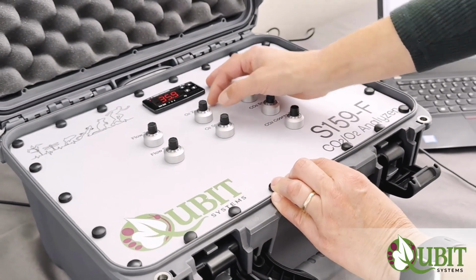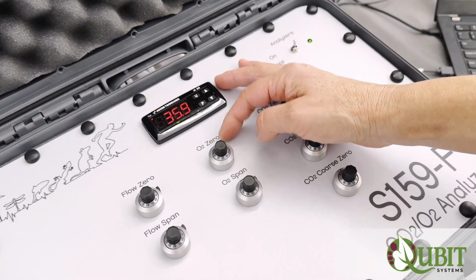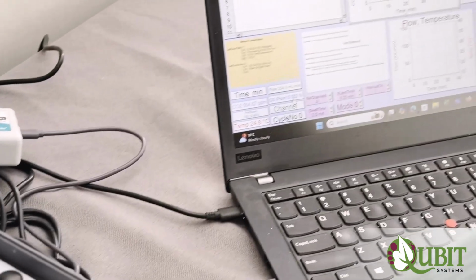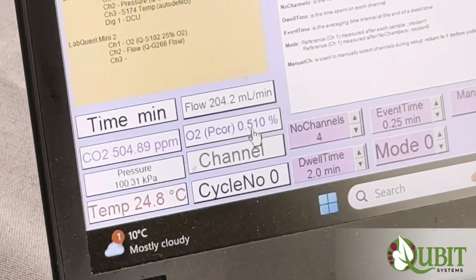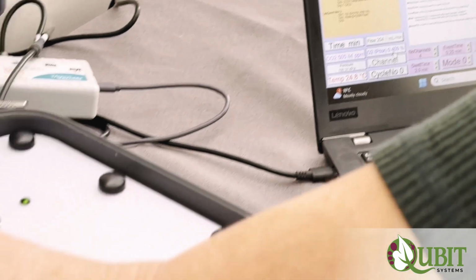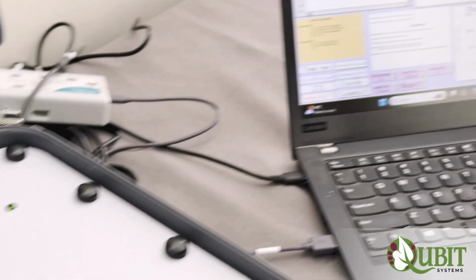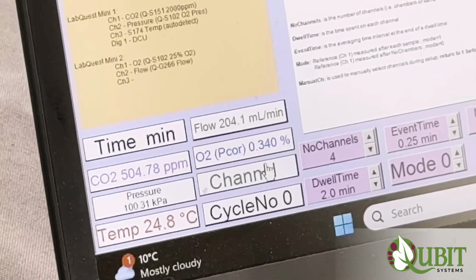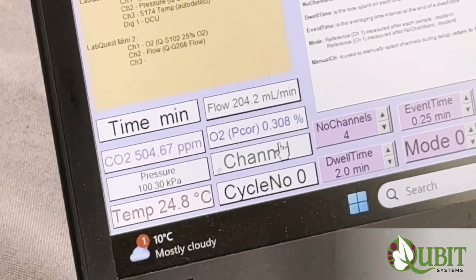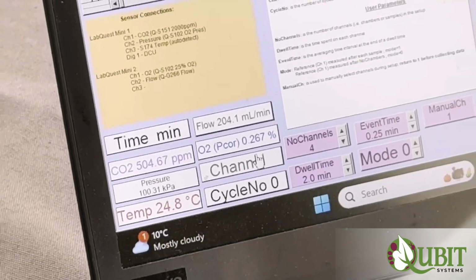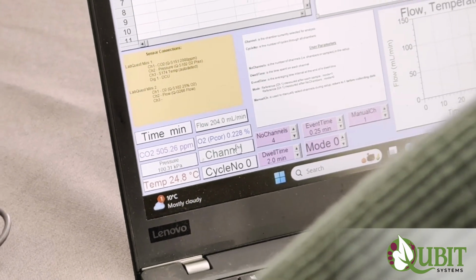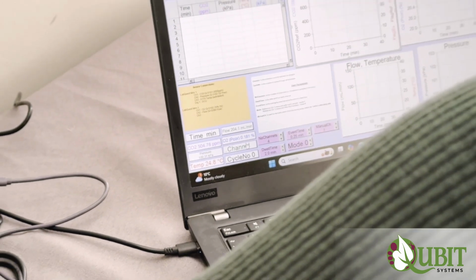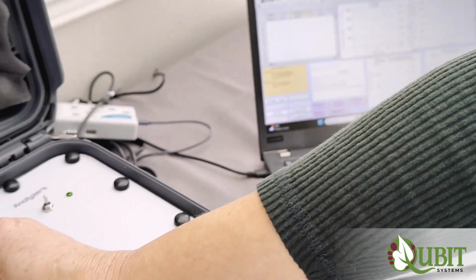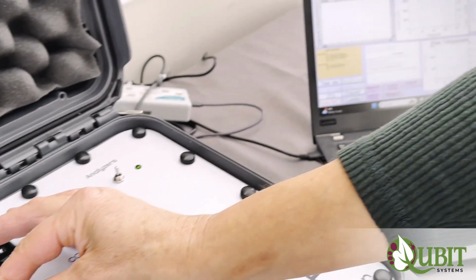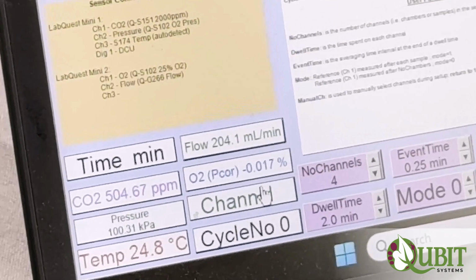We then need to go to the oxygen 0 knob. The same way, we release the tab by pushing it upwards, and then slowly turn the oxygen 0 knob anti-clockwise to reduce the reading in the software down to 0. You will notice that in the software, the reading says O2 Pcor. That stands for pressure corrected, because we have a pressure sensor next to the oxygen sensor, and with changes in atmospheric pressure, there could be changes to oxygen level as well. So we do this correction in the software, and therefore you see displayed here the corrected for pressure oxygen reading. And we're close to 0 now. Just went over. But there we are. Again, we lock this in place.